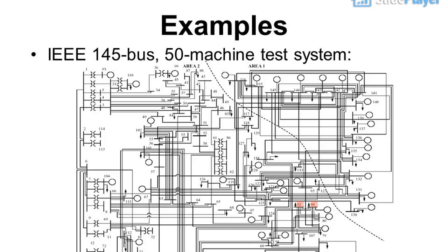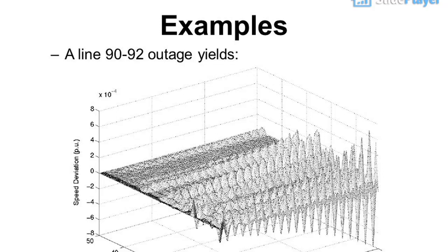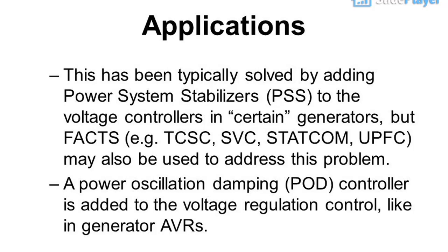Examples using the IEEE 145-bus, 50-machine test system: line 90–92 outage yields inter-area oscillations. This has been typically solved by adding power system stabilizers (PSS) to the voltage controllers in certain generators, but FACTS devices — for example TCSC, SVC, STATCOM, UPFC — may also be used to address this problem. A power oscillation damping (POD) controller is added to the voltage regulation control, like in generator AVRs.